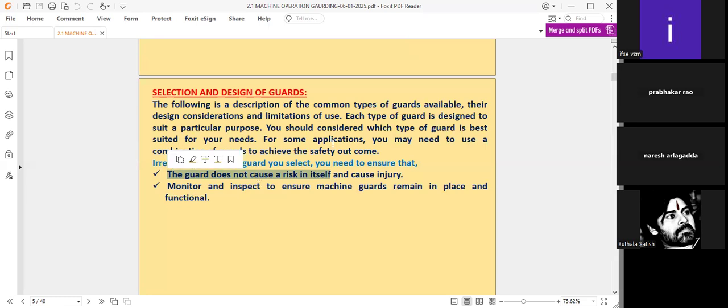As I was telling you, from the delivery line a drop of leakage in the GI sheet becomes a hole because of the concentrated liquor, the concentrated acid. It will become a risk to that guard. Once the guard is at risk, definitely the shaft also becomes damaged and causes injury or equipment damage.